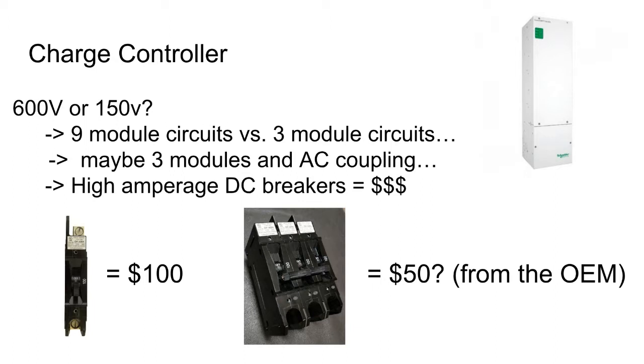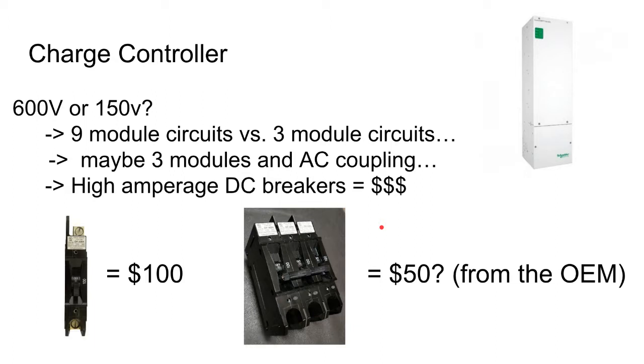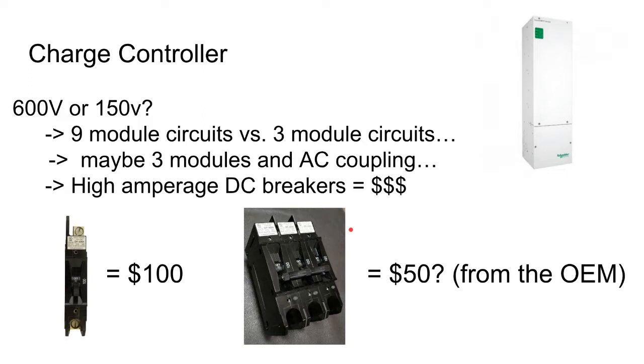So what I did is I went and looked at the breaker installed, and it's not a Schneider breaker, it was a different manufacturer listed right on the side. I plugged that into eBay and found a bank of 3 breakers that were 100 amps, single pole. It kind of looked like a triple pole breaker, and I was a little nervous when I bought it, because I didn't know if it was really a 3-phase, 3-pole breaker, or if it was what it appeared to be, which was 3 single-pole breakers kind of ganged together.